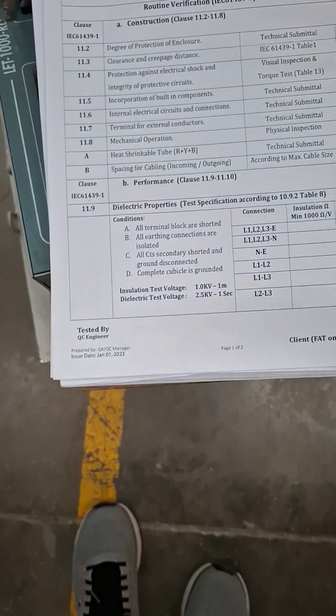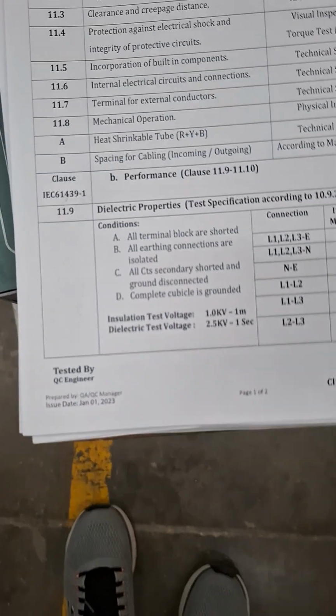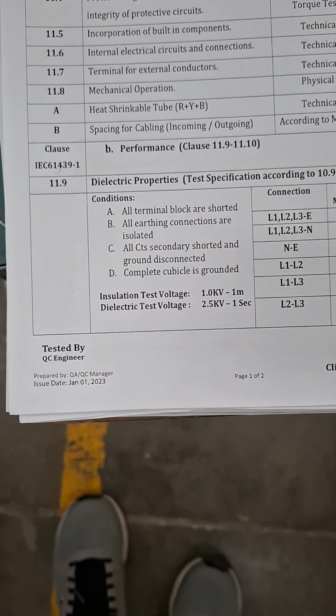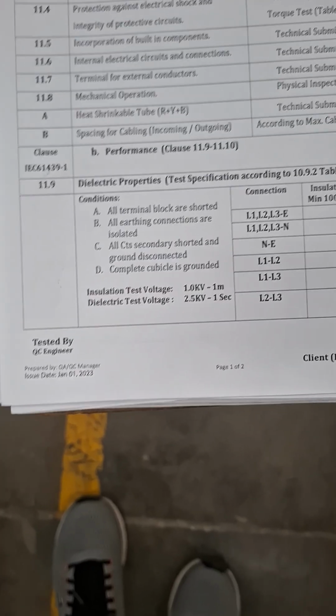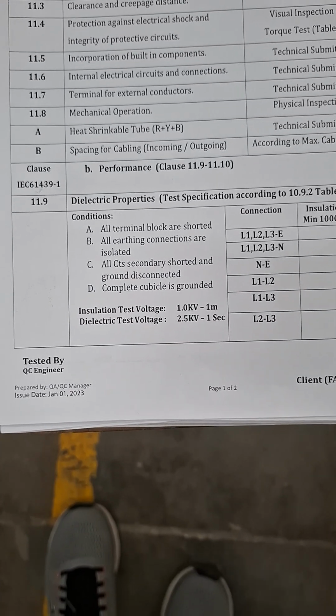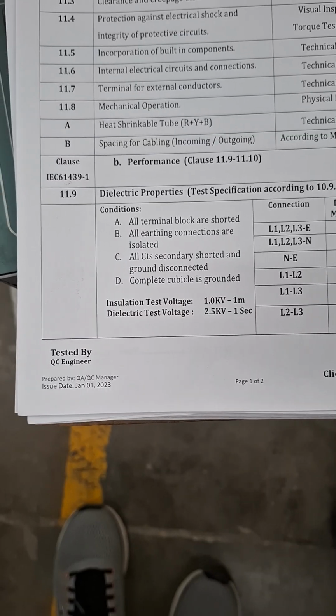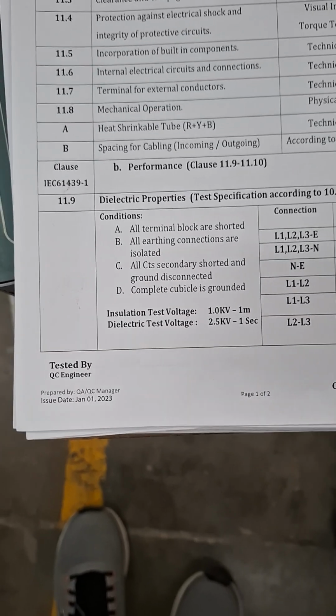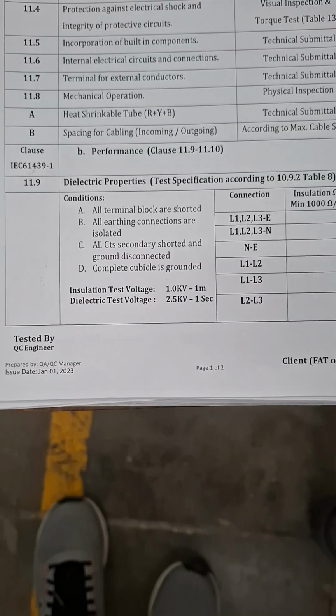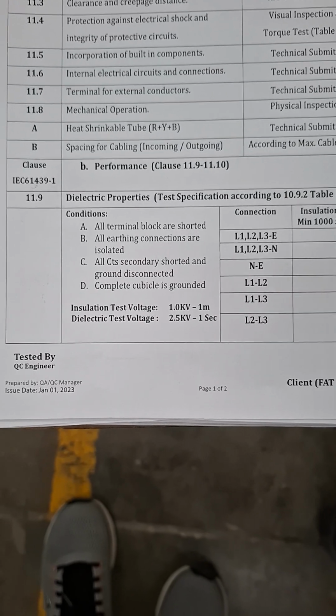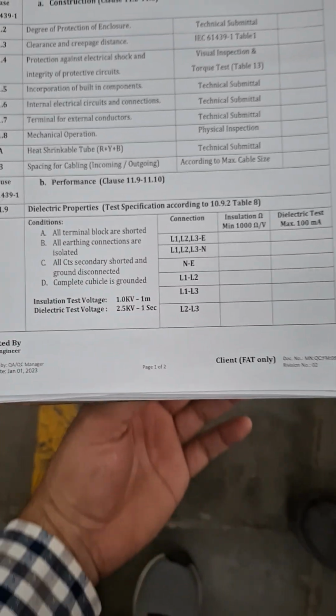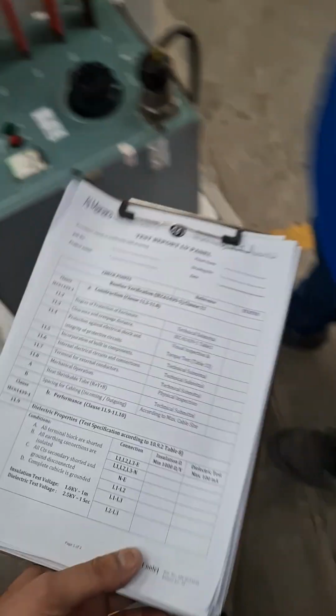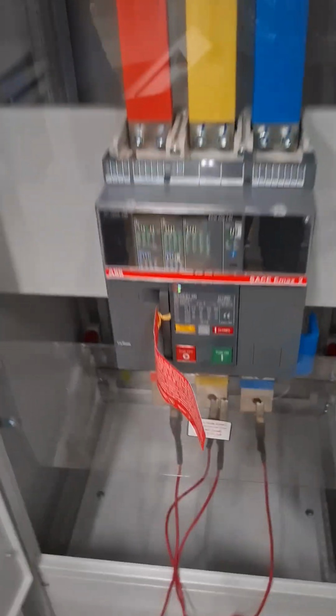One is the mega test, the other is the dielectric test. In the mega test we apply 1000 volt for 1 minute, and the minimum accepted value is 1 mega ohm. The other test is 2.5 kV AC for 1 second. Okay, first of all, our physical inspection.